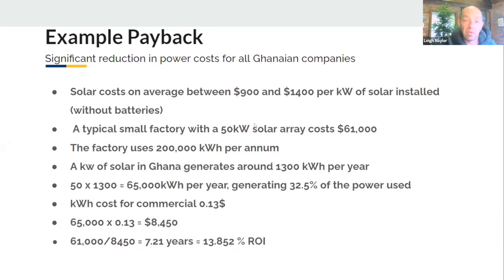So we've got a 50 kilowatt solar array, each generating 1,300 units per year. 50 times 1,300 means that a 50 kilowatt solar array in Ghana would generate 65,000 units of electric. Looking at how many units of electric you're actually using, that means the 50 kilowatt solar array would generate 32.5% of the power used in that factory. Obviously if you wanted a bigger solar array, you'd go for 100 kilowatts, and then you'd go up to 65% of the power used generated from your solar.